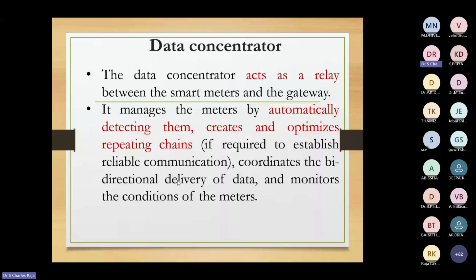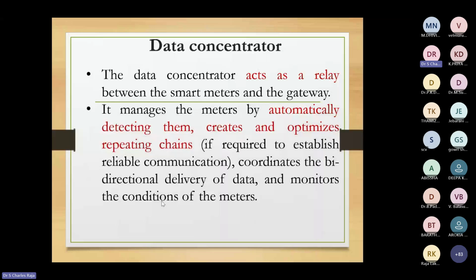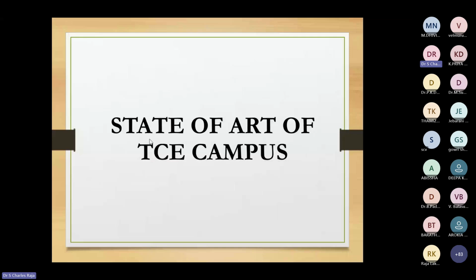It manages the meters automatically, detecting them, creates and optimizes repeating chains, coordinates bidirectional delivery of data, and monitors the condition of the meters. Usually all smart meter data is gathered through the RS-485 protocol and comes to the data concentrator. Once data is received, from data concentrator to server we usually use the LAN protocol for communication. Every data concentrator has its own IP address, so using that we can easily fetch each concentrator through LAN or wireless connection. Then the meter data management system can be done using PLC technology or GPRS based technologies. These are the basic things usually available in smart meter technology.